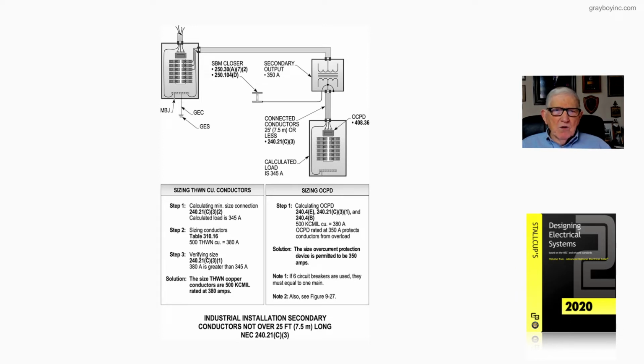And sometimes we may have to go up to 250% here due to inrush current, based upon the transformer's design and so forth. Or maybe we just want to increase it to 250% because this secondary side feeds and supplies a lot of fractional horsepower motors that if we size the overcurrent device for the largest and added the remaining fractional horsepower motors to it, we couldn't raise this overcurrent device up based upon the motor calculation, so we could use it and size it by table 450.3(B) based upon transformer rules and regulations.